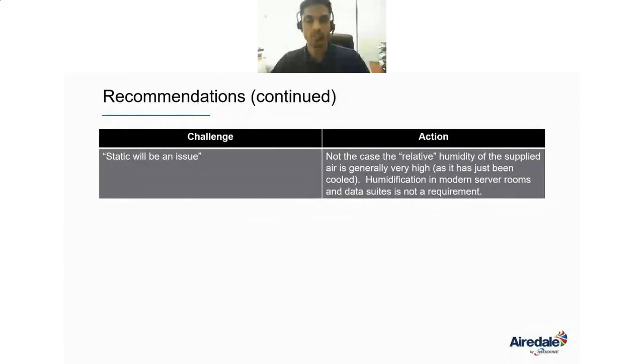Static will be an issue. So this is basically about electrostatic discharge. That is not the case, because the relative humidity at the supply temperature is very, very high, since the air has just been cooled, usually above 90%. So humidification in modern server rooms at these temperatures is usually not a requirement.